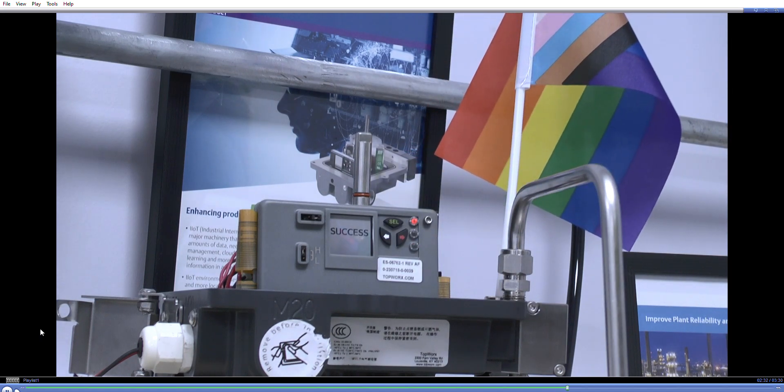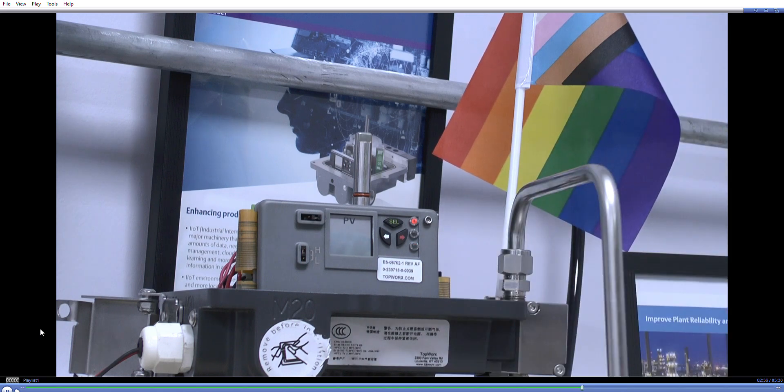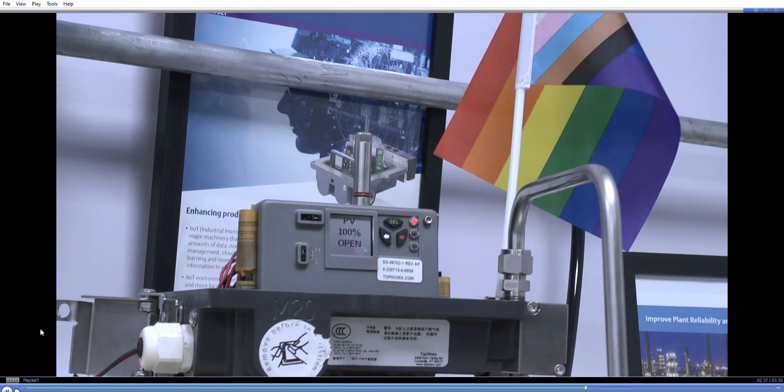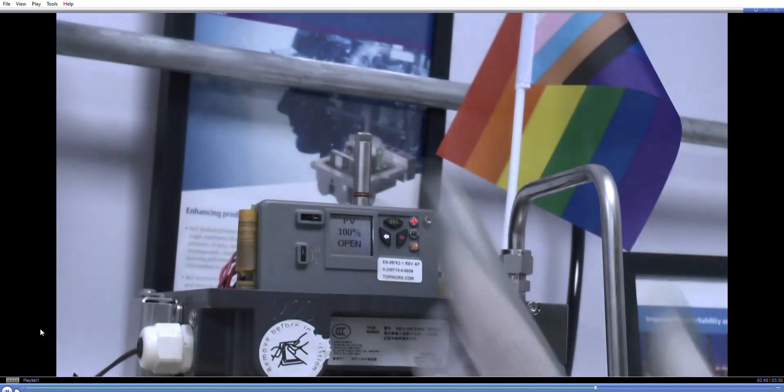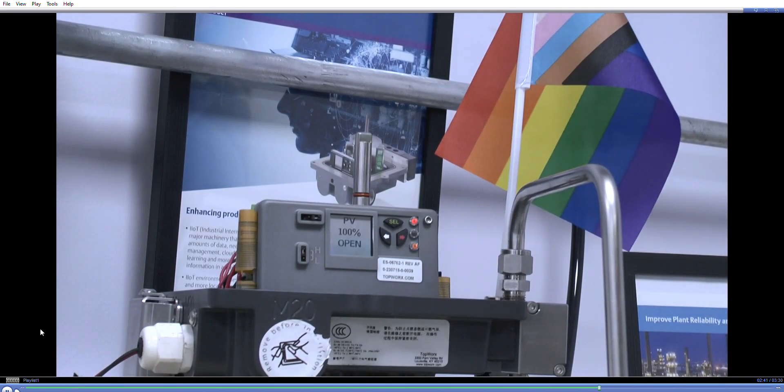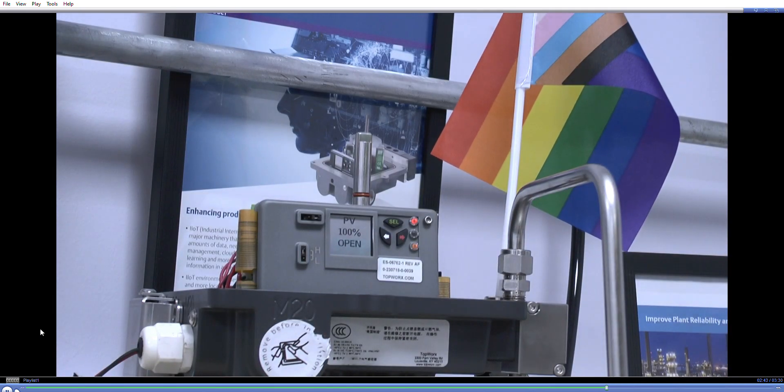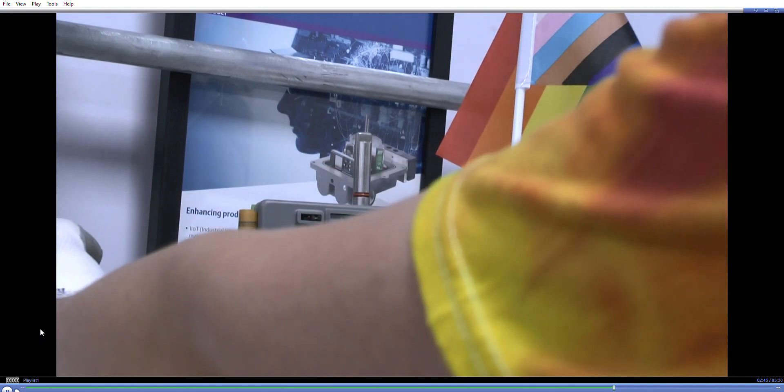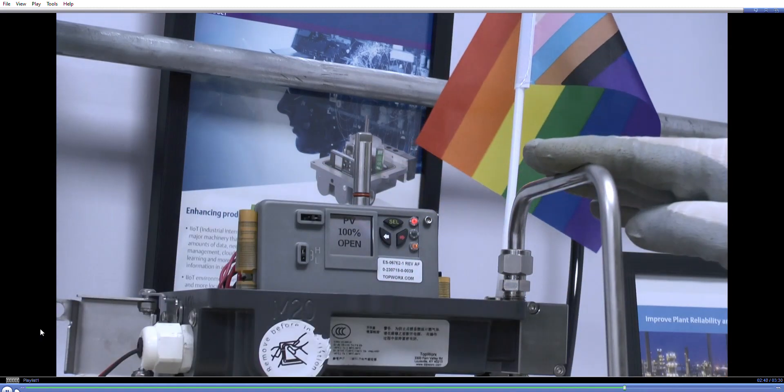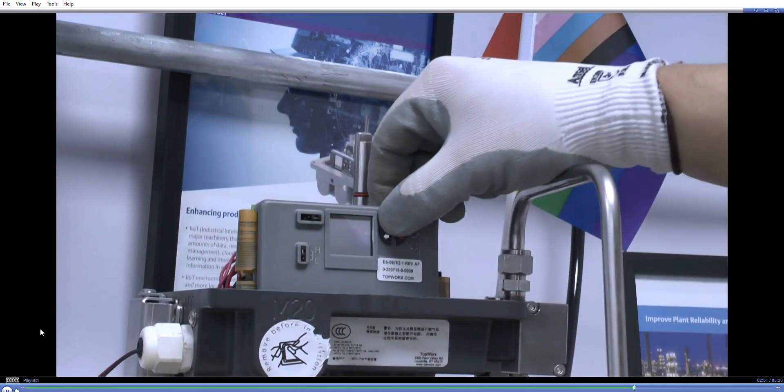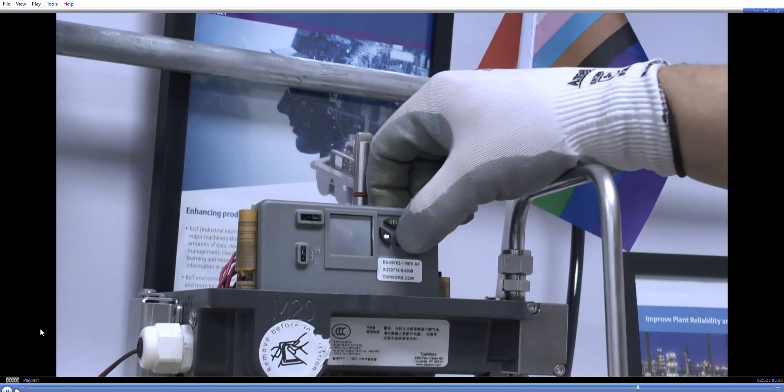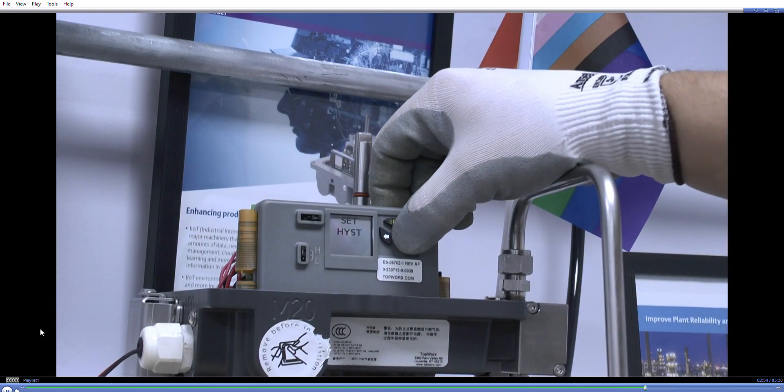So there we go, it's just tested and done a partial stroke calibration. Because we've already calibrated the valve, then we do the partial stroke test. And then what we're able to do, you can initiate that obviously via the system, via the control system or by the button on the side that initiates a partial stroke test, and I believe you can also do it through the menu again.